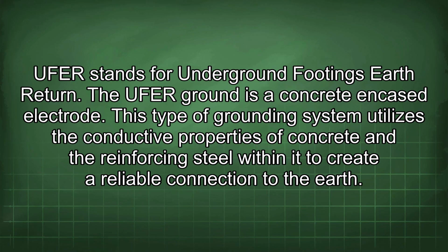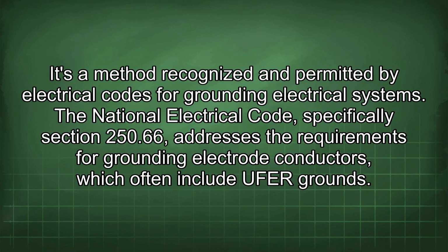UFER stands for Underground Footings Earth Return. The UFER ground is a concrete encased electrode. This type of grounding system utilizes the conductive properties of concrete and the reinforcing steel within it to create a reliable connection to the earth. It's a method recognized and permitted by electrical codes for grounding electrical systems.